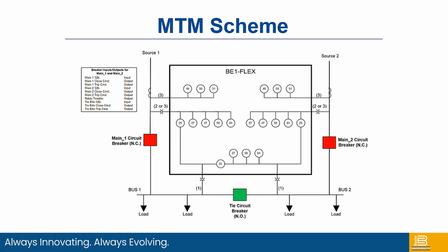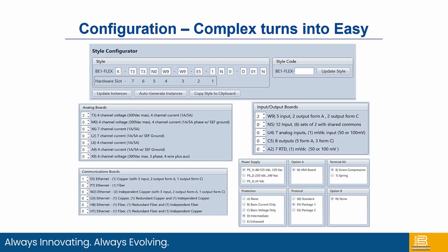One of the things that I do mention quite often is you're not going to slow the Flex down. You can't put in so many functions that the processing is going to slow down. There's even a capacity meter in the settings file or in the settings explorer that will show you that you are within the bounds, and the Flex will not allow you to send up a settings file that is going to slow it down and make it do more than it can do. So there's protections there to make sure inadvertent errors don't occur.